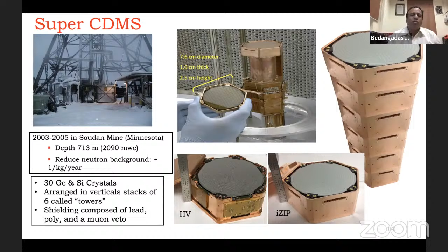Broadly, the detector volume is inside this green shaded region. It's a cryogenic detector, so it's cooled by using a dilution fridge, and additional cooling is also required. You can see from the top how the detectors are arranged, or a cross section on the top right, and on the lower right is a cross-sectional view. These are mounted on a spring-loaded platform for seismic isolation.